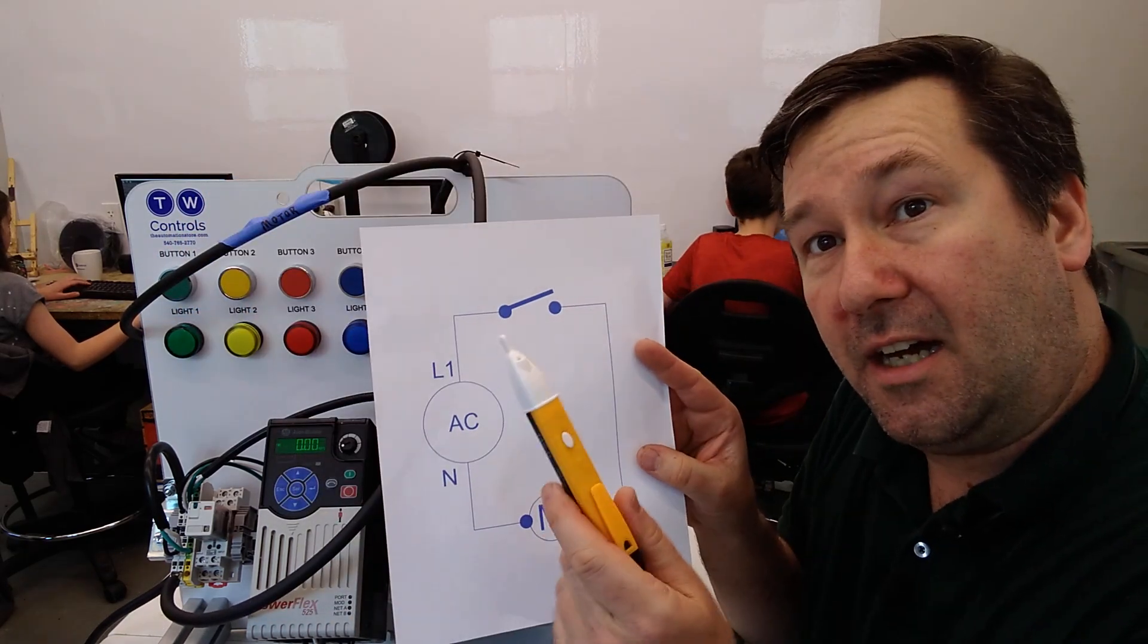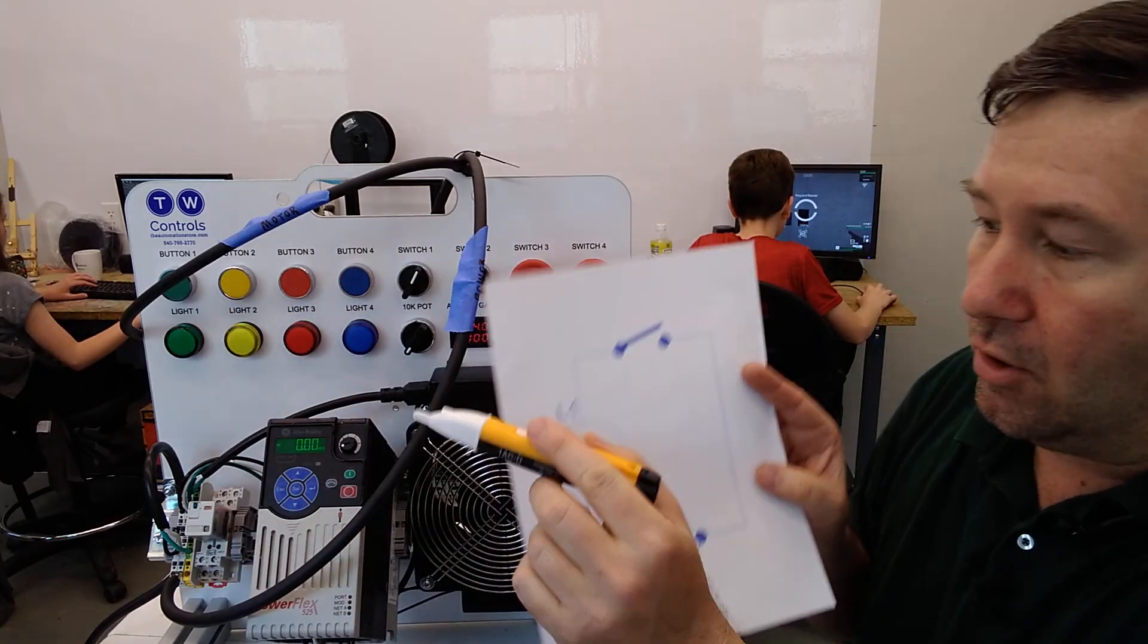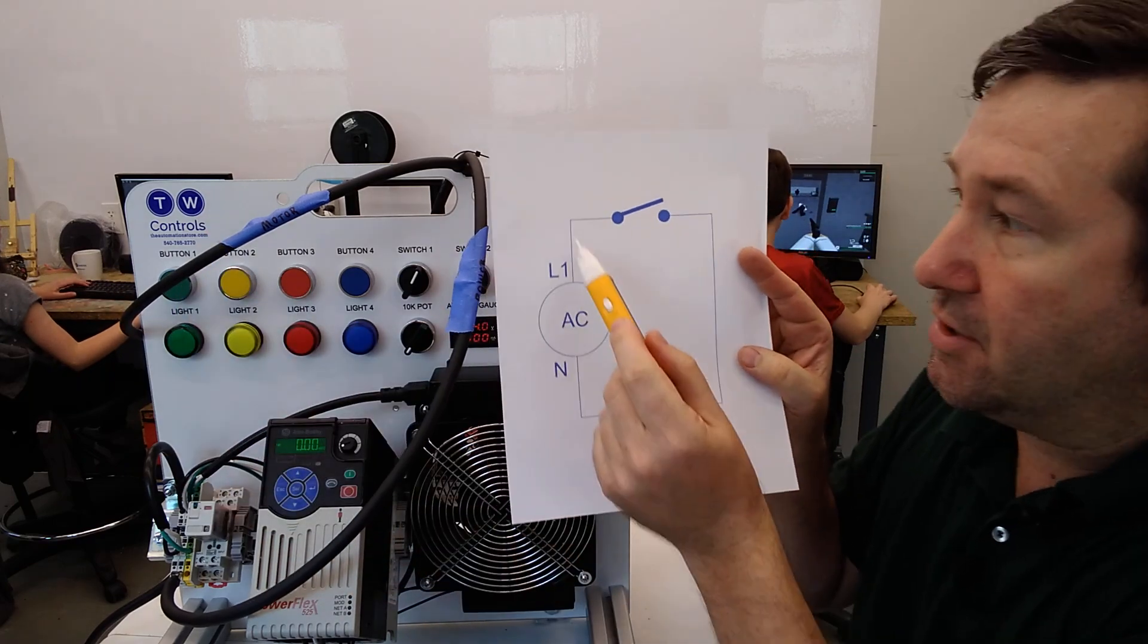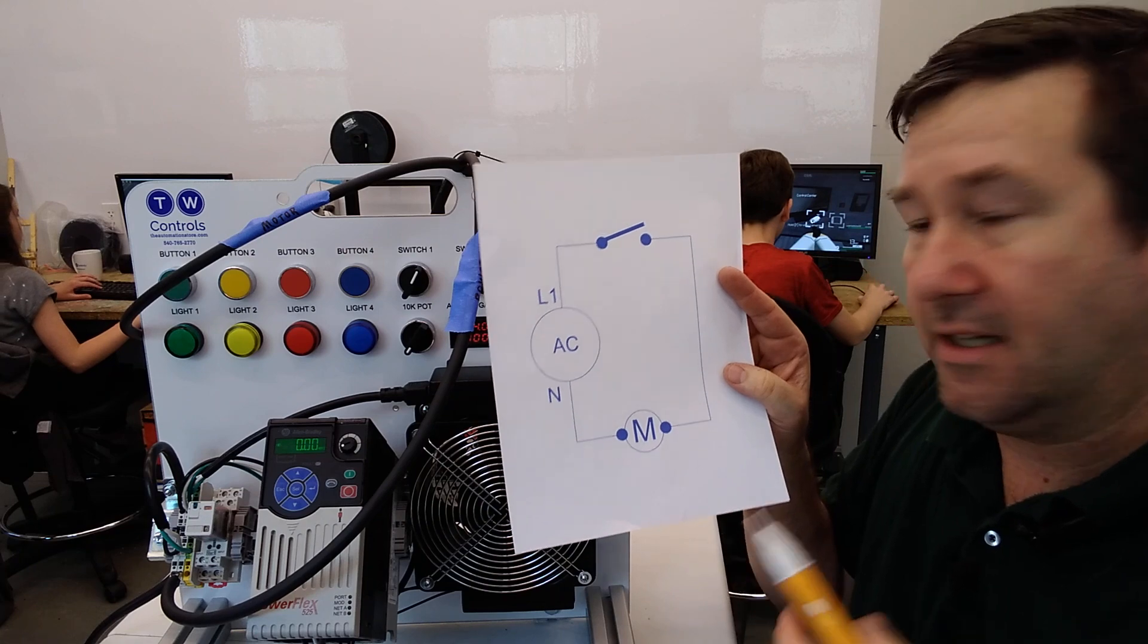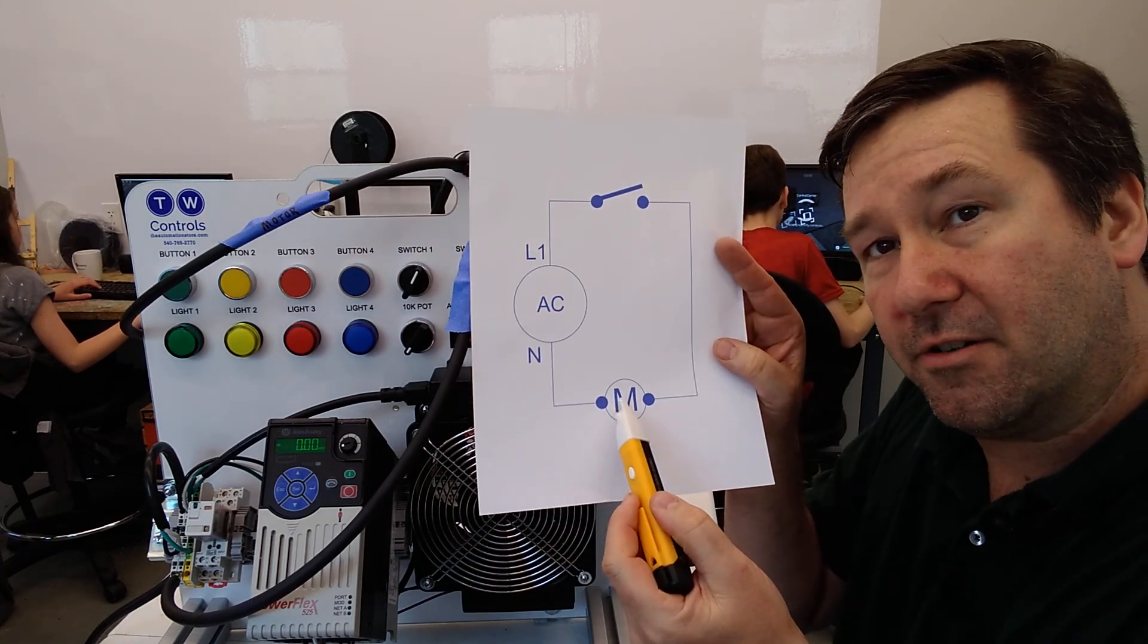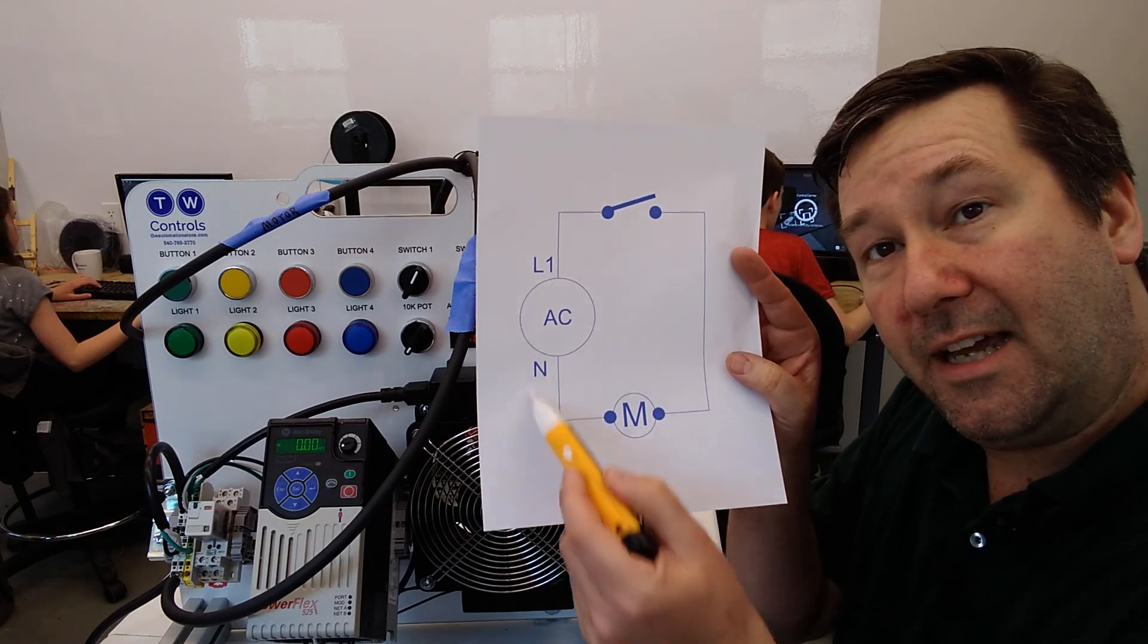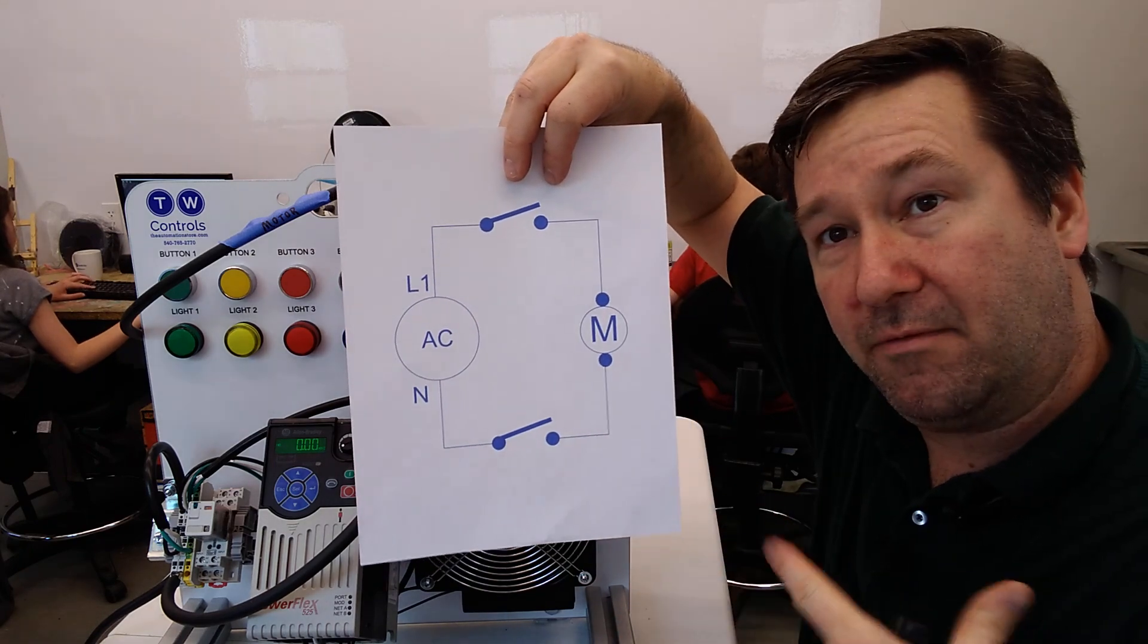So in the case of our non-contact voltage sensor, we're checking that we have power, which is right here, and that our switch is good because we have power on this side. So it looks like we have power to our motor, but just like on our sinking and sourcing videos, this last little bit of the leg often gets forgotten. And what we found out, it was actually this circuit.